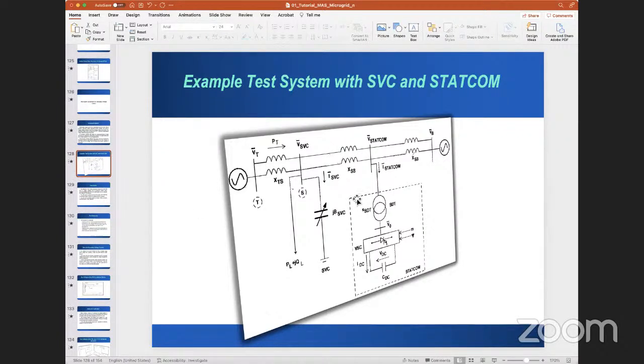We saw that when you have this kind of system, you have SVC here, and then STATCOM here. And when SVC is fully injecting its capability to maintain the voltage, and when this voltage is still below its limit, violating it, this agent goes to the STATCOM agent. And STATCOM agent is seeing good voltage at its bus, so it's not doing anything, right?